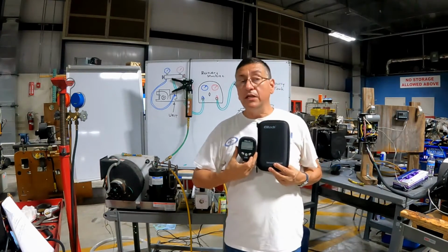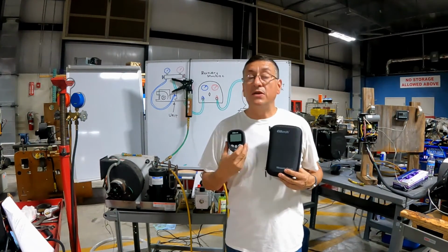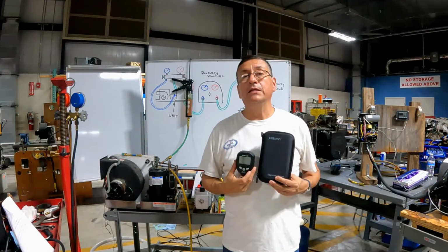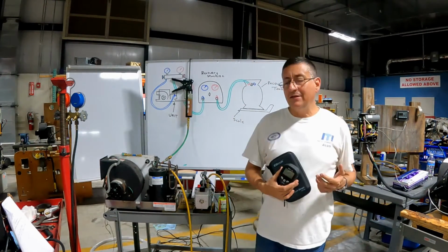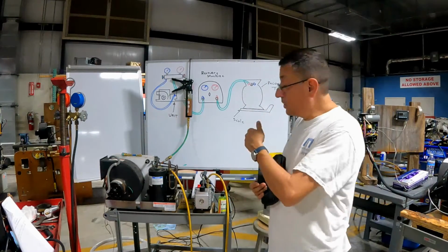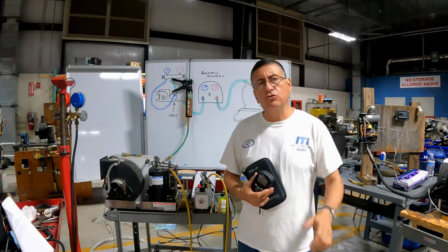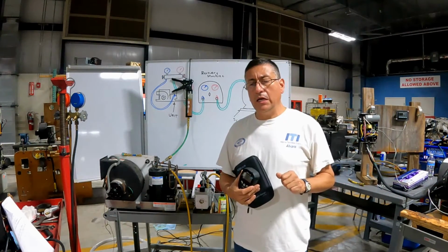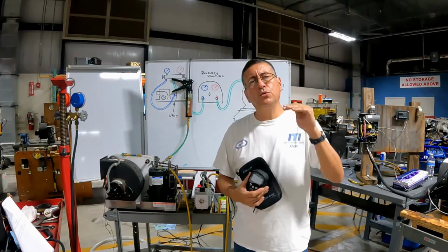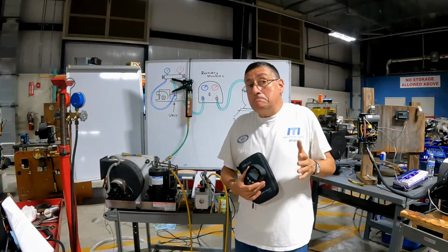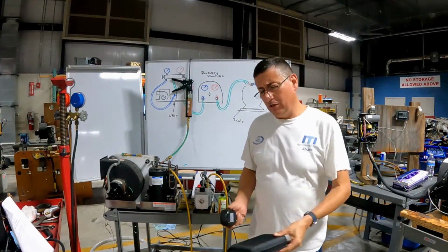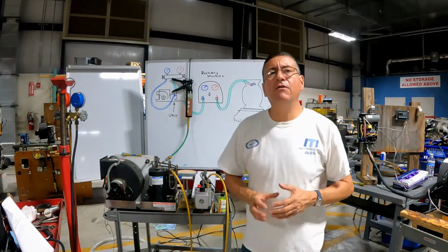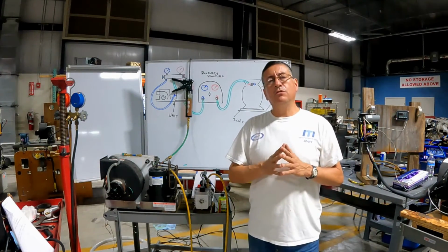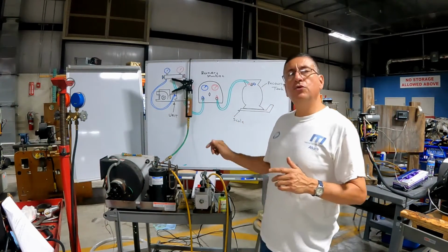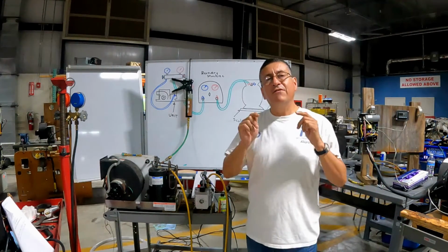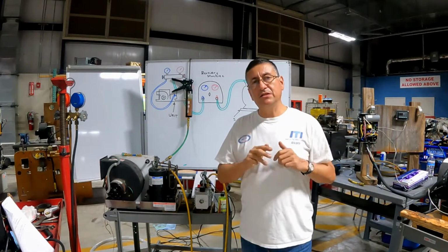The vacuum gauge is critical in order to determine if the process is complete. The majority of technicians say, no, I connect my vacuum pump for 40 minutes, for 1 hour, and with 1 hour, I am 100% sure that the vacuum is complete. Probably not. Why not? It depends on whether you have leaks. For that reason, one of the most important parts before you do the vacuum process is to verify that you don't have leaks on the system.